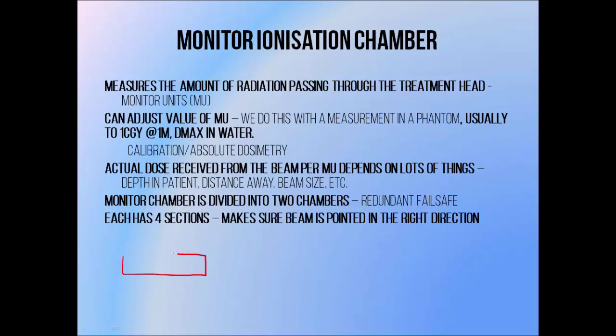Below the scattering foil or flattening filter is a monitor chamber. The monitor chamber is an ionization chamber, which is a device for measuring amounts of radiation. The beam passes through it before it leaves the treatment head, allowing the monitor chamber to keep track of the amount of radiation leaving the linac. This allows us to pre-set how much radiation we want to deliver using a given beam, by telling the machine to shut off after the monitor chamber measures a certain amount of radiation.